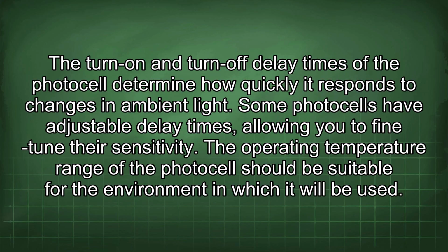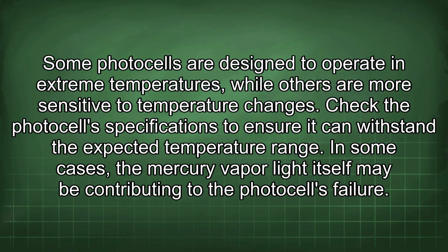Some photocells have adjustable delay times, allowing you to fine-tune their sensitivity. The operating temperature range of the photocell should be suitable for the environment in which it will be used. Some photocells are designed to operate in extreme temperatures, while others are more sensitive to temperature changes. Check the photocell specifications to ensure it can withstand the expected temperature range.